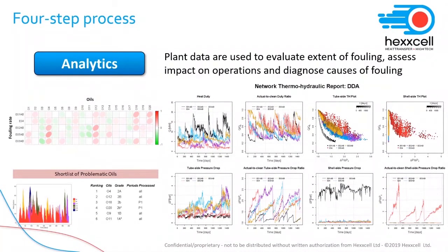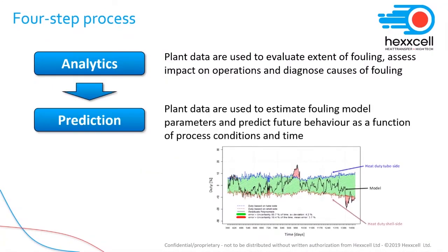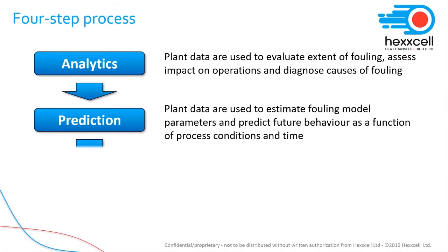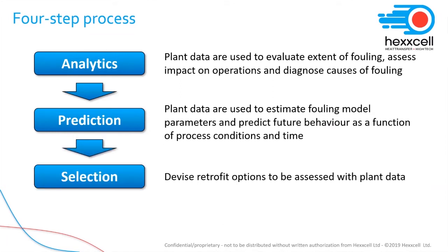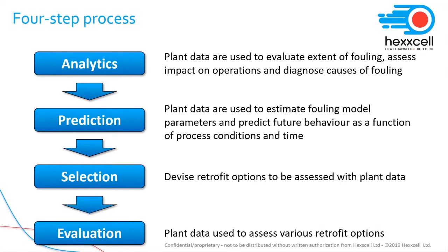This is really a four-step process, whereby we take past plant data, we run detailed analytics, and assess the impact of fouling on operations from both a thermal and a hydraulic point of view. We identify performance issues, potentially diagnose causes of fouling, calculate the reference conditions with no fouling, which enables us to quantify its economic impact, as well as identifying which are the heat exchangers better suited for retrofit. In the next step, plant data are used to estimate the fouling model parameters so that we can be confident in the predictions and that we are correctly capturing the fouling behavior over time. The following step is the selection of alternative options to test, for example, new configuration of one specific heat exchangers or different network arrangements. And then we use the plant data with our dynamic simulations to assess these options and stack them against each other.